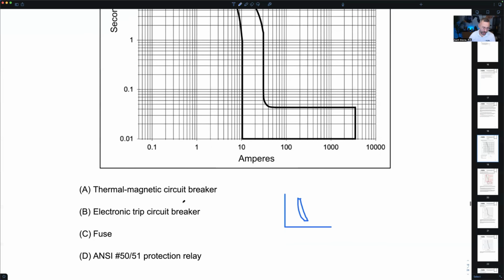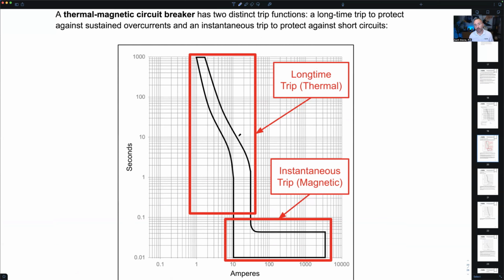So how do we know? How is this a thermal magnetic circuit breaker? Thermal mag breakers really only have two distinct trip functions, or we can say two distinct time current curve characteristic regions, right? Who here works on thermal mag breakers? What's one of the most common applications? What's one of those common applications of what we typically just call a thermal mag?